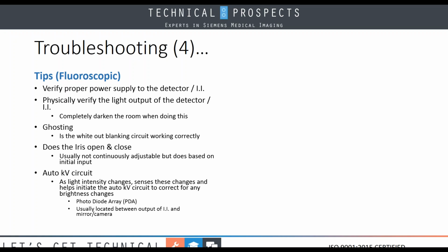Quickest way for you, put some different density and different thickness objects in the beam, work it through. It should be responding very, very quickly. If it's too much of a delay, this is an indicator that possibly your sensor, your photodiode array, or your photomultiplier tube may be going bad.